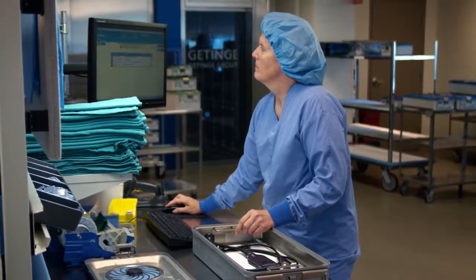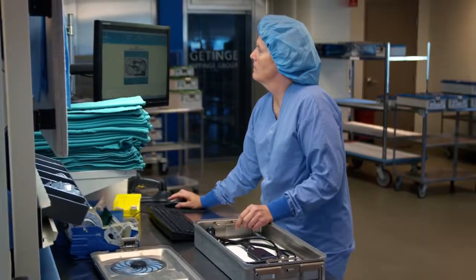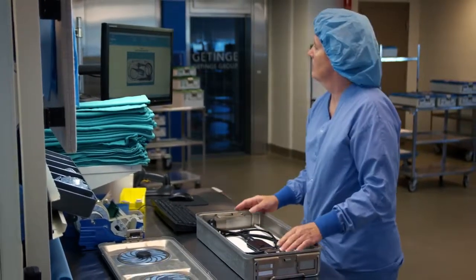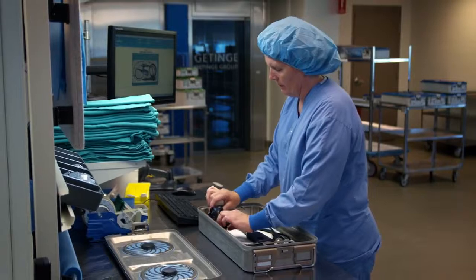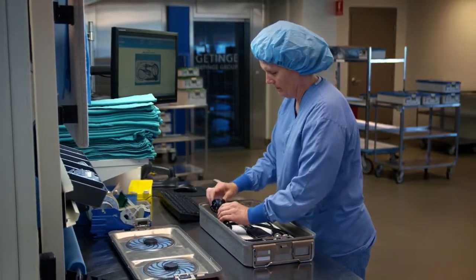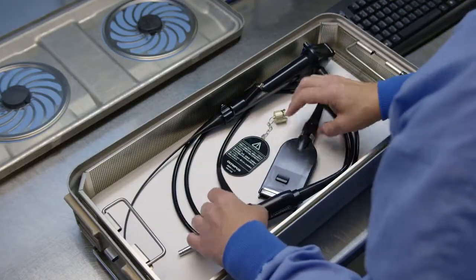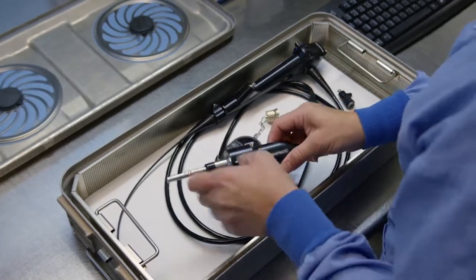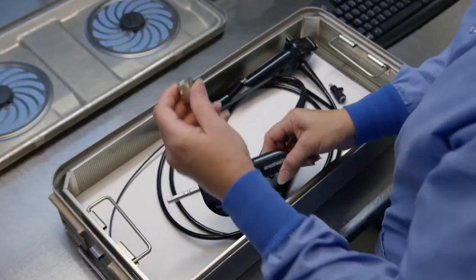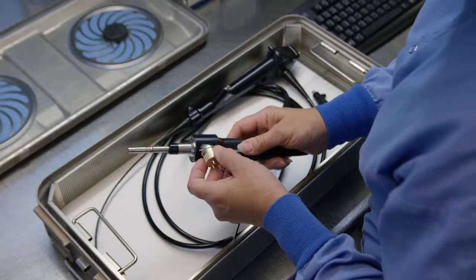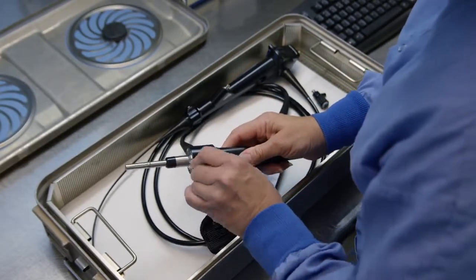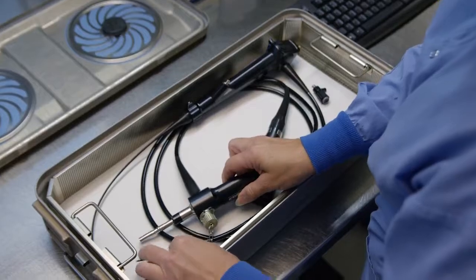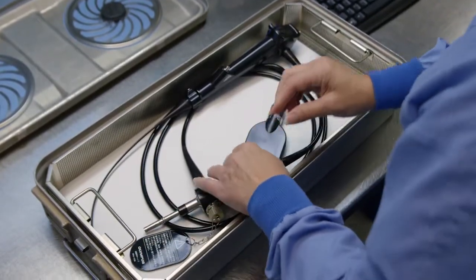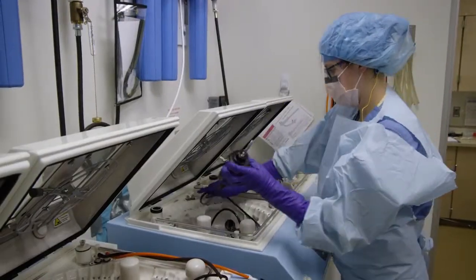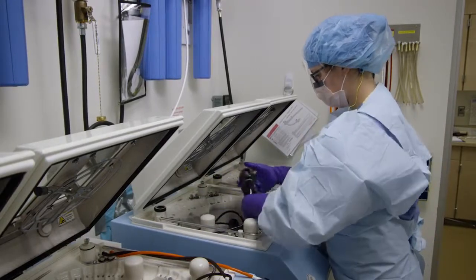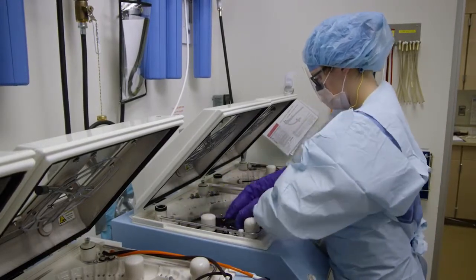Ethylene oxide, or ETO sterilization, is the most common sterilization process for flexible endoscopes, as it's the most compatible with delicate, heat, and moisture-sensitive medical devices. When packaging for sterilization, be aware that most endoscopes require the attachment of an ETO vent cap provided by the endoscope manufacturer to prevent damage from the vacuum in the sterilization chamber. According to Spaulding's theory, when sterilization is not possible, use high-level disinfection.